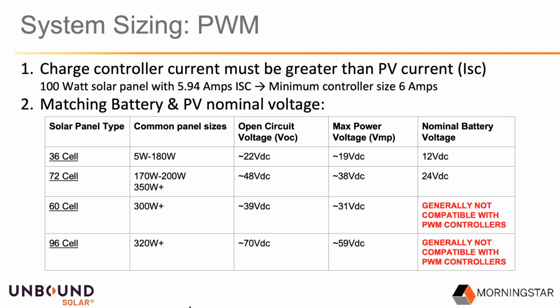The next row, the 72 cell panel, is essentially the same thing but doubled. That's a nominal 24 volt panel. These are the only two sizes that were really designed to work with a PWM controller. The voltages for those panels were designed specifically to charge batteries through a PWM controller, so there are no issues as long as we pick the corresponding panel and battery voltage. It's going to work, and it's pretty simple.